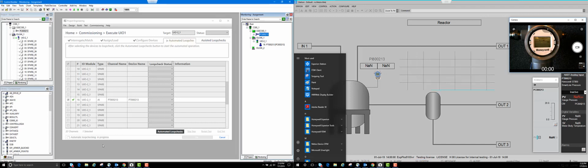So about another 30 seconds or a minute or so, then we should see on the information column here, to the most right, that populate with loop check in progress, meaning that the service has instructed the instrument to send the 0 to 100% output to the DCS to do the 5-point test. And then here in a few more seconds, we should see this turn green. After it displays loop check in progress, this control strategy will turn green, and the loop check will start.